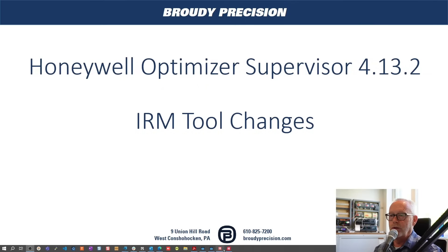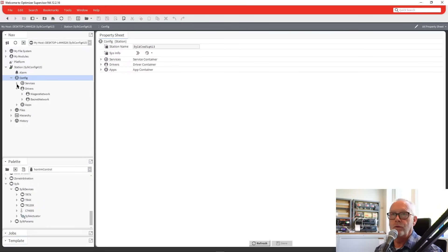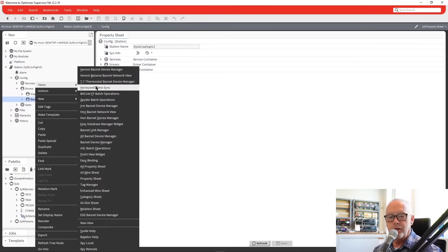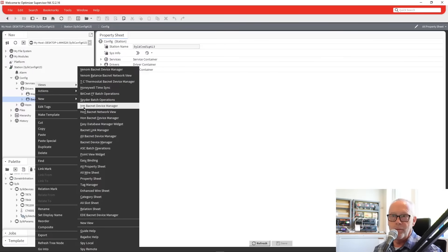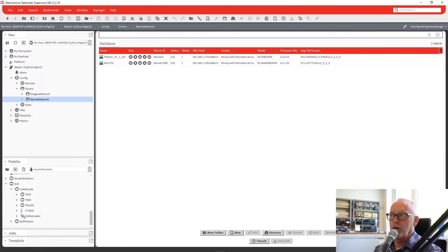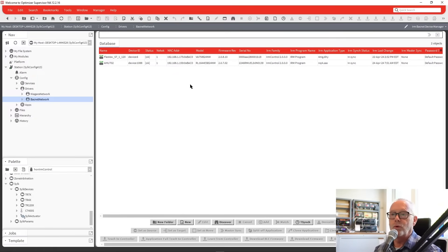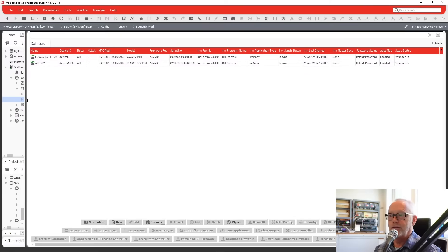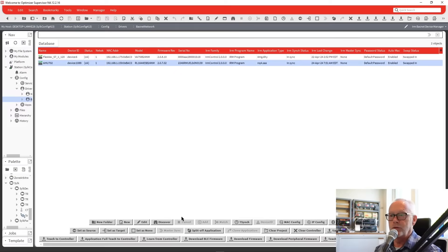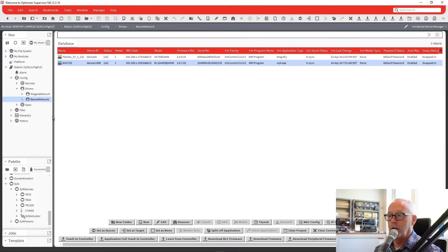I'm going to compare it to a 4.12.2 Optimizer software. When you go to your BACnet network and you're programming the Spyder 5 and 7 VAVs and the Unitary Controller, you work from the IRM BACnet device manager view. If you double-click on BACnet network, it only brings you to the HON BACnet device manager, and you would normally go in and select the IRM tool. Once you go there, you'll notice there are 33 different buttons that you use with the controllers.